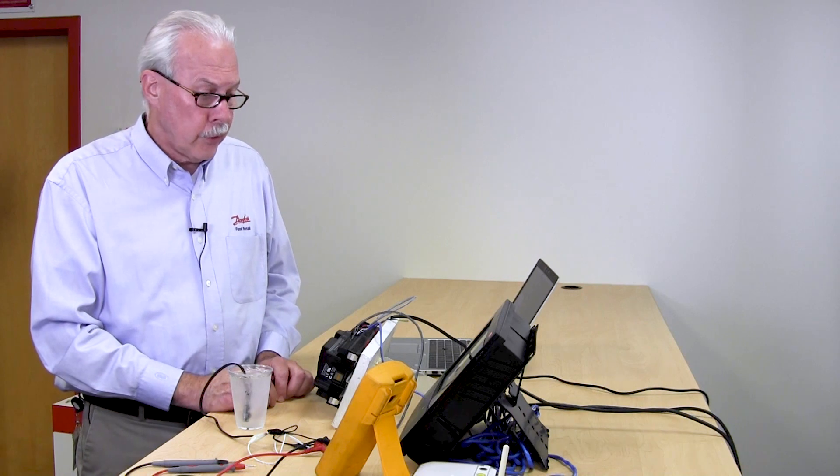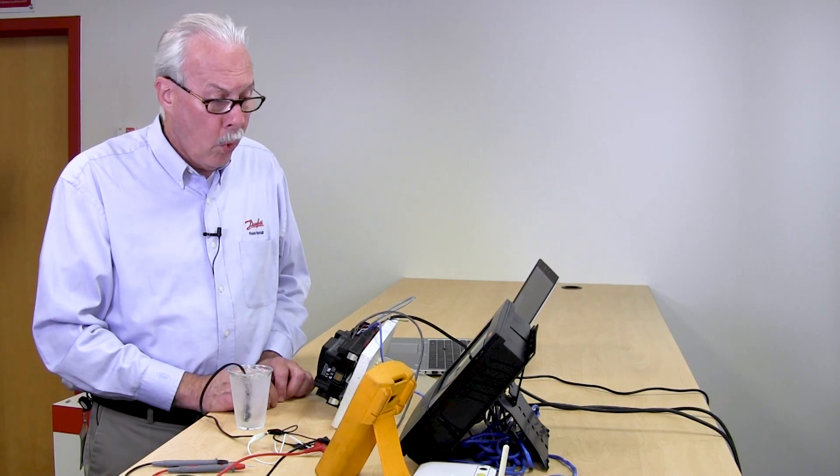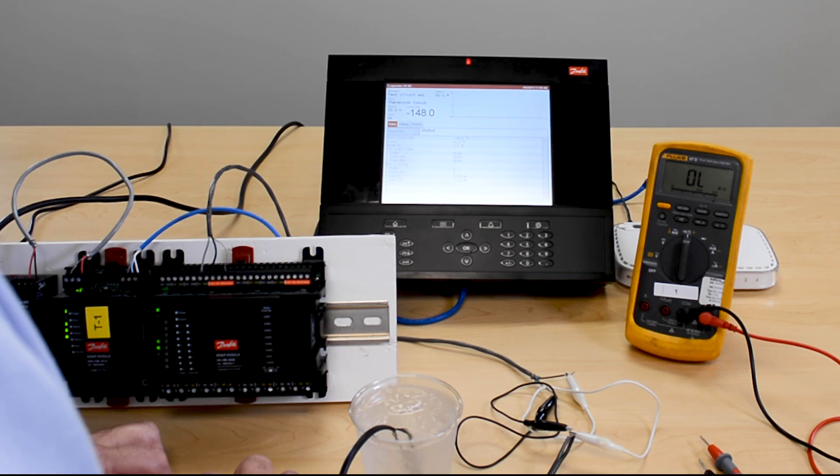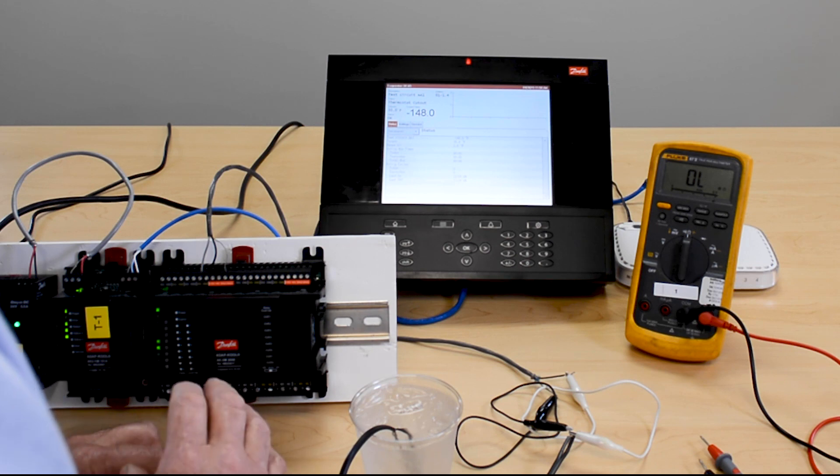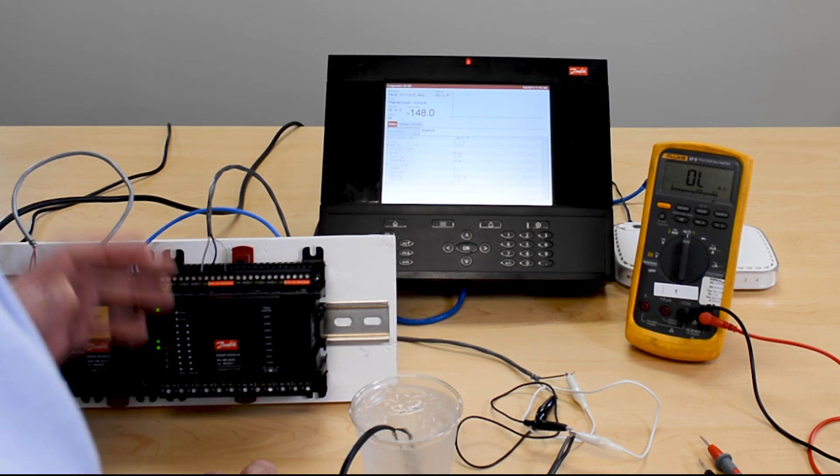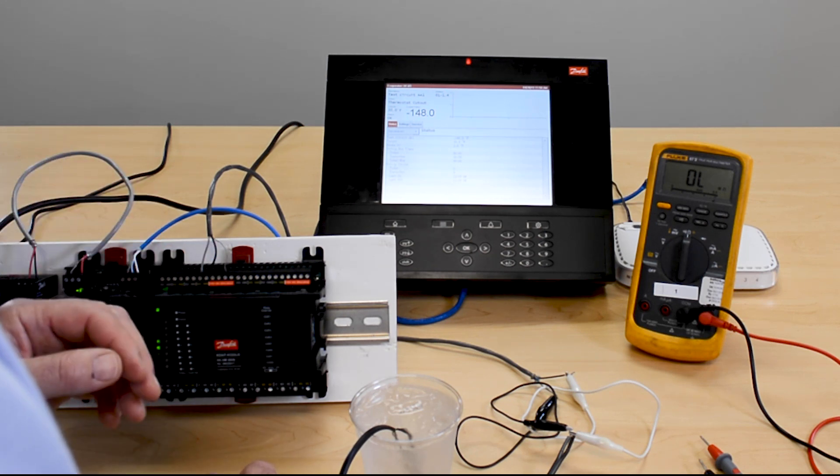So now we're going to start troubleshooting to find out why we have a short. We've come into the store and see that we have minus 148 on the display, telling us that somewhere from the system manager down to that case, we have a shorted condition. The best way to troubleshoot is to isolate your problem and possibly divide this troubleshooting into two pieces.